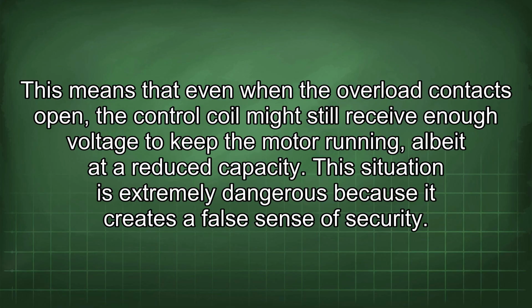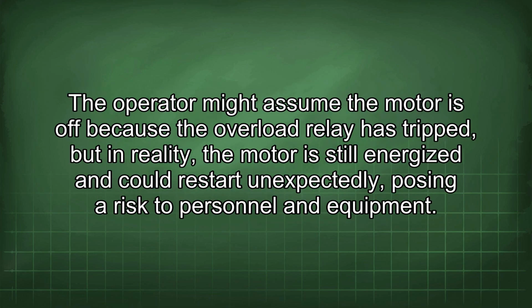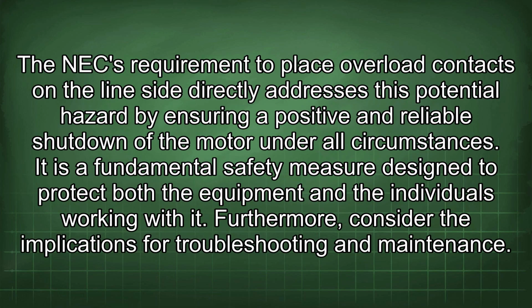This situation is extremely dangerous because it creates a false sense of security. The operator might assume the motor is off because the overload relay has tripped, but in reality, the motor is still energized and could restart unexpectedly, posing a risk to personnel and equipment. The NEC requirement to place overload contacts on the line side directly addresses this potential hazard by ensuring a positive and reliable shutdown of the motor under all circumstances. It is a fundamental safety measure designed to protect both the equipment and the individuals working with it.